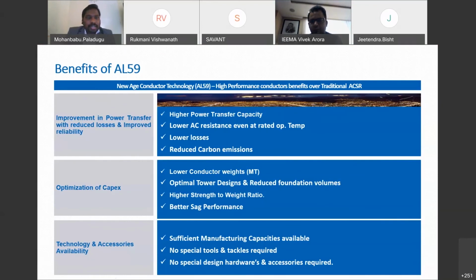Sir, as we seen in the last slide, we are talking about the ampacity and weights and losses part. So if you categorize those overall benefits of AL59, in the last presentation also we have seen similar benefits. So improvement in power transfer capacity with reduced losses and improved reliability, which we have seen here, 20 to 25% higher power transfer capacities. So with lower losses, lower AC resistance values, at the 50% loading, which is the normal operating condition, the losses are lower compared to ACSR, which in turn reduces your total carbon emissions in the country.